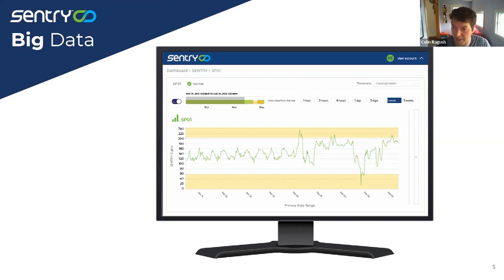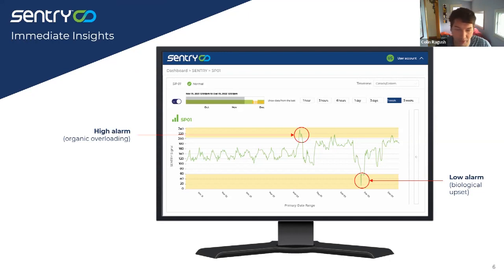What we also will pick up is peaks and troughs. Quite often the peaks are high organic overloading events. We see peaks because our biology is eating more carbon, and we see troughs because usually there's some form of upset. So some sort of contaminant or chemical has come in that is disrupting the metabolic activity. And it's great to be able to see this and pick up events, but there's so much more that can be done with this data.